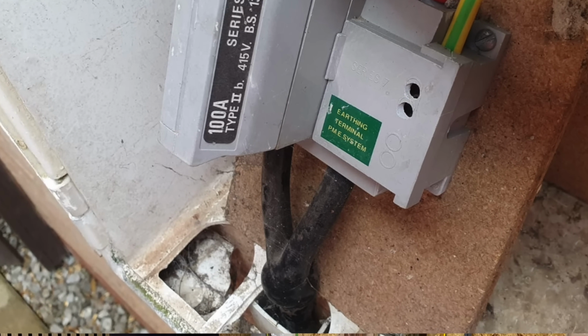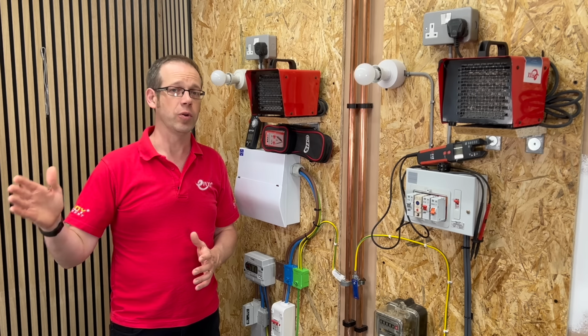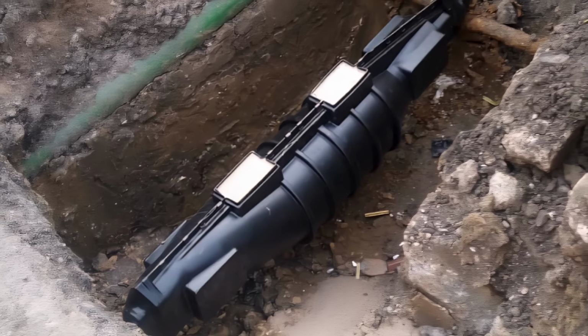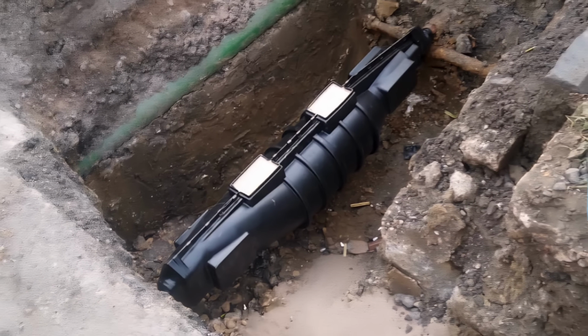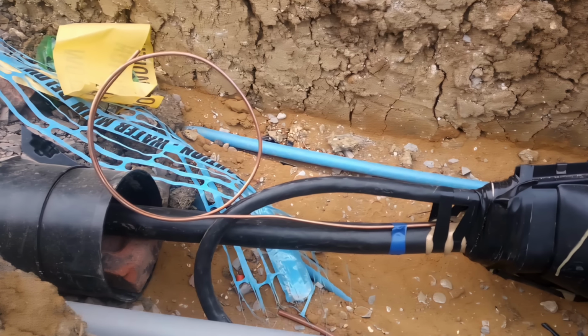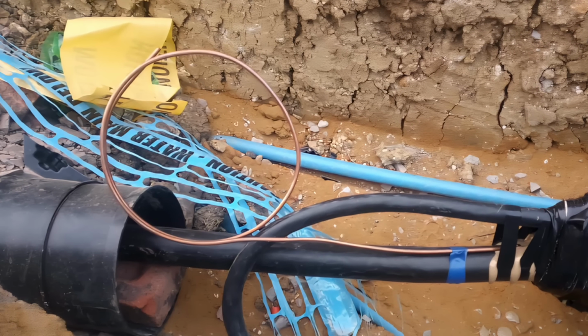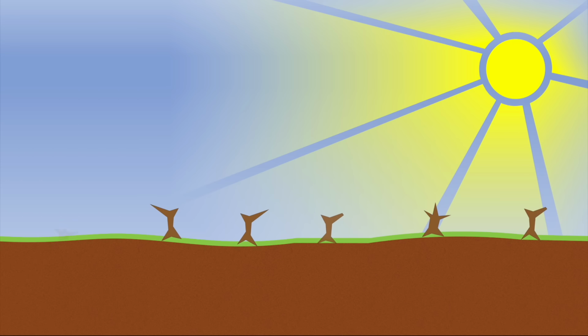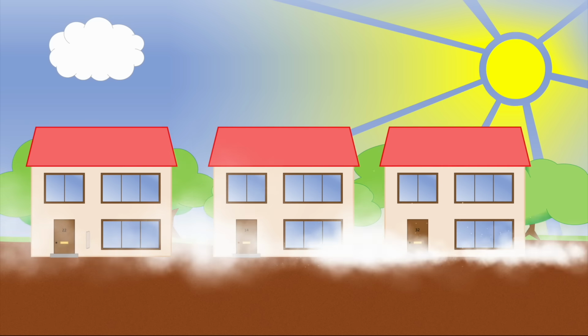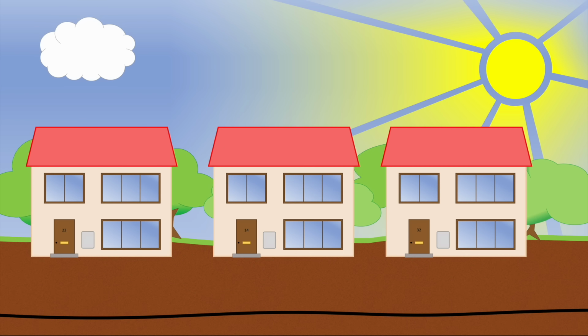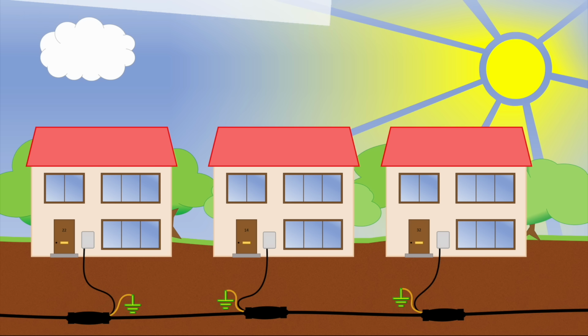These come from the street, where they connect to the main supply cable from your local transformer via joint boxes that are buried in the ground. At the point where this connection is made, the DSO connect the combined neutral and earth conductor directly to the general mass of earth. That's the earth we walk around on. Because they do this at every connection from the supply cable, it gives us multiple earth connections along the protective conductor. That's where we get the expression protective multiple earthing, or PME.